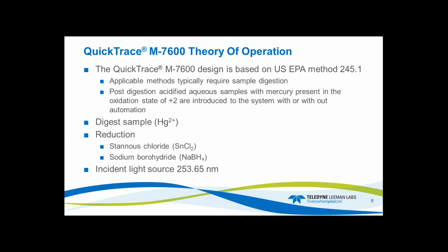The 7600 base design is for EPA 245.1. Again, that goes back to Hatch and Ott, the whole theory there. It's applicable to methods that typically require sample digestion. So in post-digestion acidified aqueous samples, mercury will be present in the +2 oxidation state, and that's introduced to the system with or without automation. So the digested sample must have Hg2+, and then we reduce it with stannous chloride or sodium borohydride, and the incident light source is at the standard mercury wavelength of 253.652.